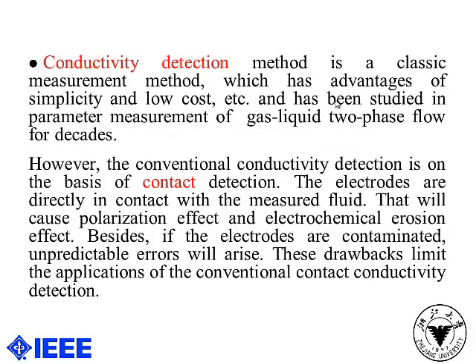Conductivity detection method, as a conventional measurement method, has been studied in current measurement of gas-liquid two-phase flow for many years. However, for conventional conductivity detection, the electrodes are directly in contact with the fluid, which will cause the polarization and electrochemical effect. Besides, if the electrodes are contaminated, unpredictable errors will arise. This drawback limits the applications of conventional conductivity detection.